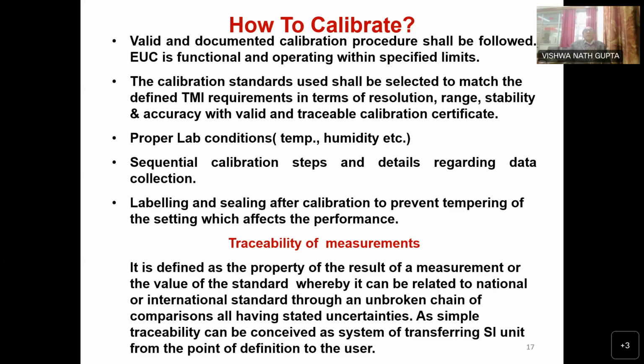So the proper lab condition should be there, sir. Proper lab condition means temperature and humidity. For electrical calibration, it is very much important. The temperature of the laboratory should be maintained. The supply output should be stabilized. Your earth to neutral voltage should be below 1 volt. Your earthing resistance also should be less than 1 ohm. So the electrical calibration laboratory needs to be very precise and should have very proper lab conditions for the measurement. I am just giving an example, sir.